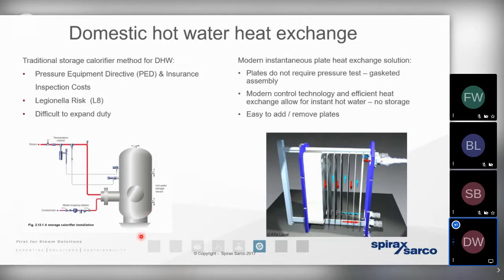But holding that hot water in storage can bring a lot of challenges for our clients. For example, if we're holding water on the secondary side at a high temperature, it's got to be held under pressure, and therefore it's got to fall under the Pressure Equipment Directive. And if we're holding water at a high temperature, there's a risk of Legionella. It's going to fall under the L8 requirements. So that's going to bring quite a lot of risk and also a lot of inspection and water treatment requirements.